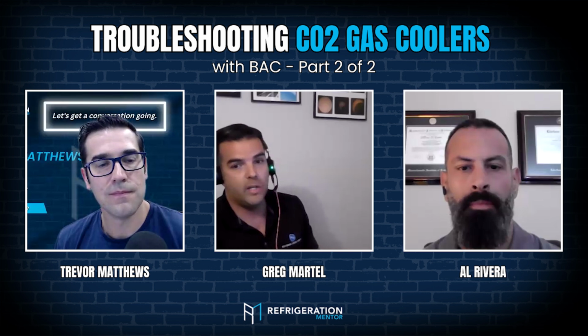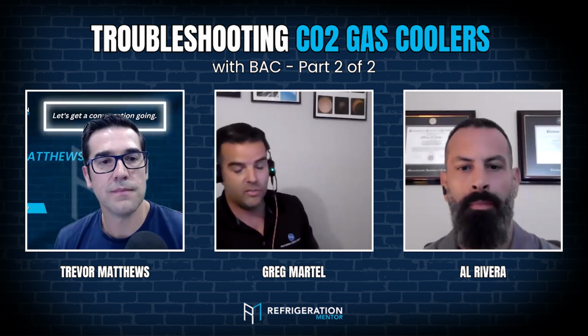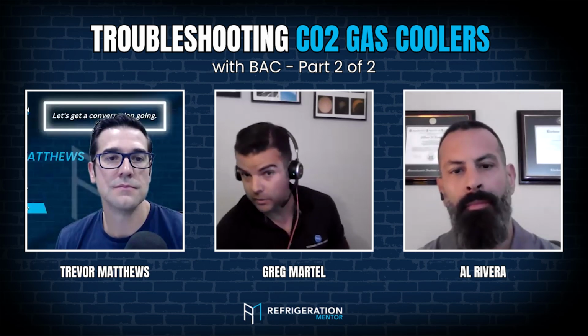On our microchannel coils, we could see expansion of up to 3/4 of an inch on the hot gas side of the coil. So imagine your coil doing this for 6 months, a year. You're wasting energy, you're damaging your unit, and obviously your compressors probably don't like that either, to be cycling like that.